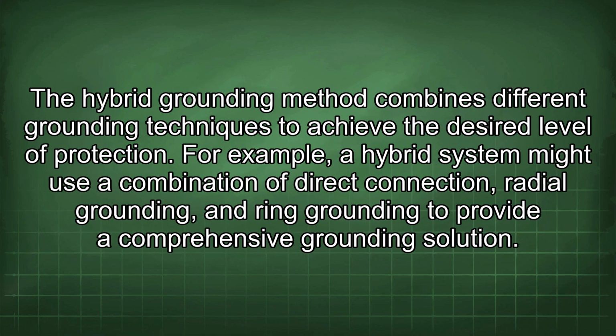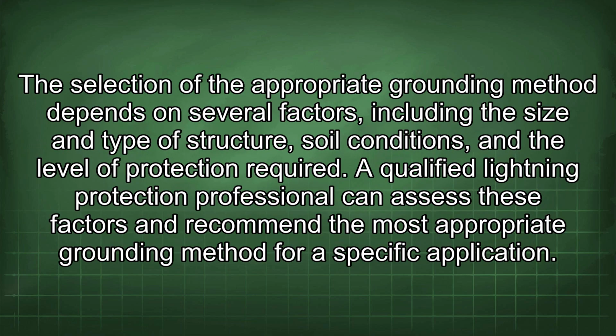The hybrid grounding method combines different grounding techniques to achieve the desired level of protection. For example, a hybrid system might use a combination of direct connection, radial grounding, and ring grounding to provide a comprehensive grounding solution. The selection of the appropriate grounding method depends on several factors, including the size and type of structure, soil conditions, and the level of protection required. A qualified lightning protection professional can assess these factors and recommend the most appropriate grounding method for a specific application.